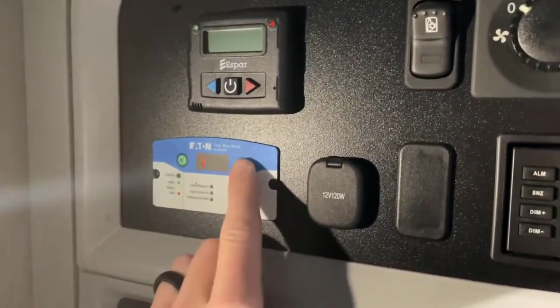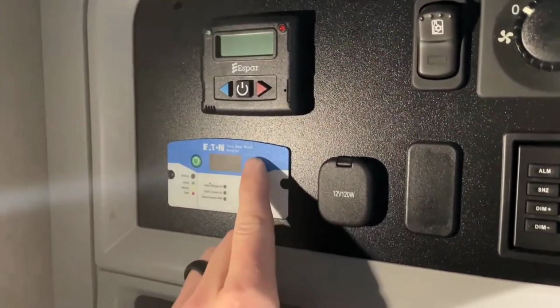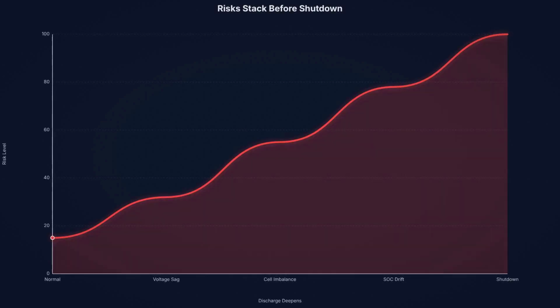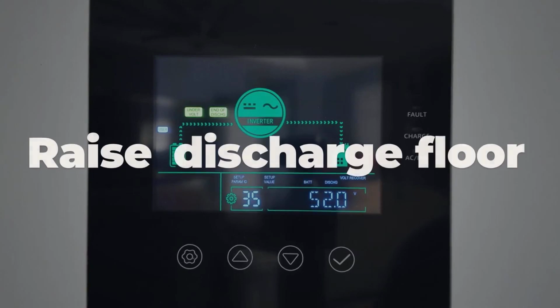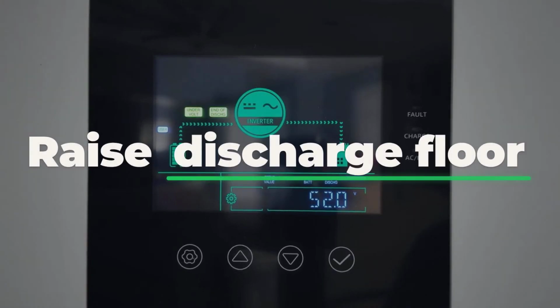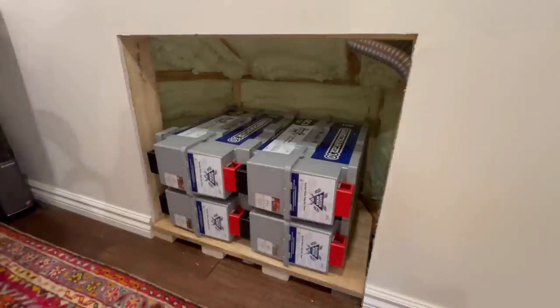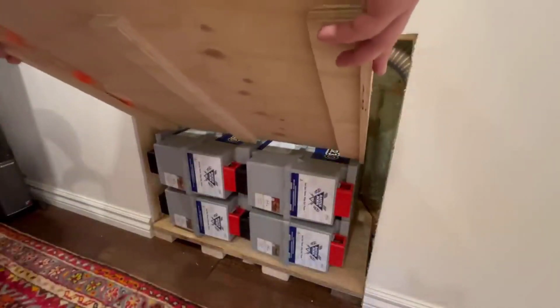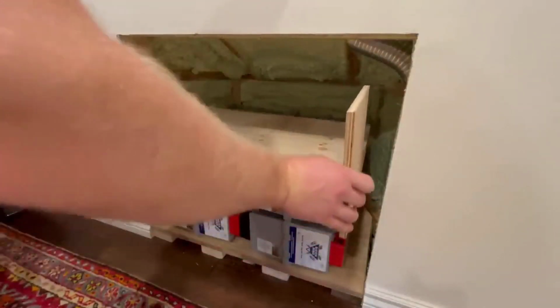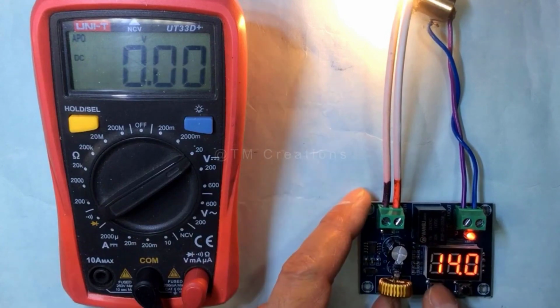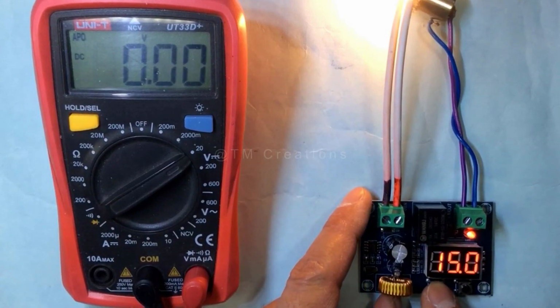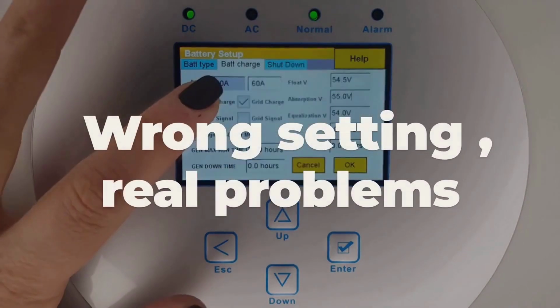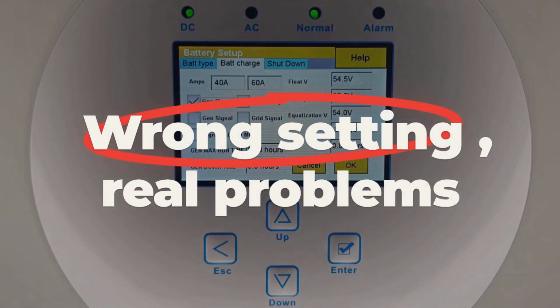Going deeper pushes the system further into the zone where voltage sag, cell imbalance, and state of charge drift already create the conditions for a crash. Raising the discharge floor keeps the system above that zone. The shutdowns stop not because the battery got better, but because you stopped asking it to operate where it was always going to fail. Raising the discharge floor is the right direction, but the number you pick matters, and picking it wrong in either direction still causes problems.